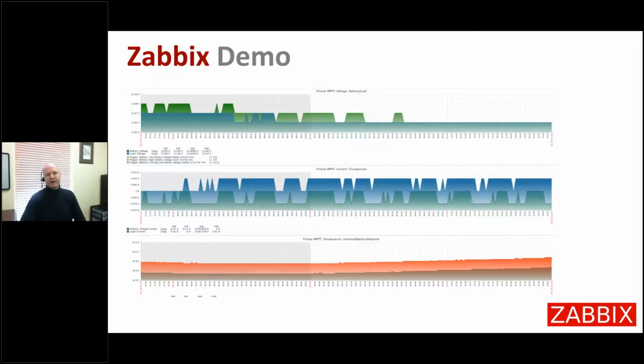If you see that you have 20 sites in pretty much the same area, but one of them is reading a lot of anomalous data that's completely different from the rest of the sites, but everything else is expected to be the same, why is that unit standing out amongst its peers and not performing? Is there damage to a module? Is there a battery cell failure? Something is different about that. And you'll see that those pieces of information start to jump out when you've got all of this data available to you. So it's extremely powerful.